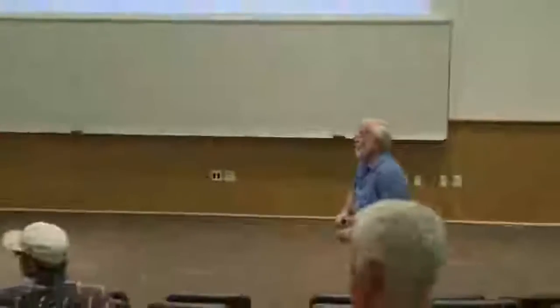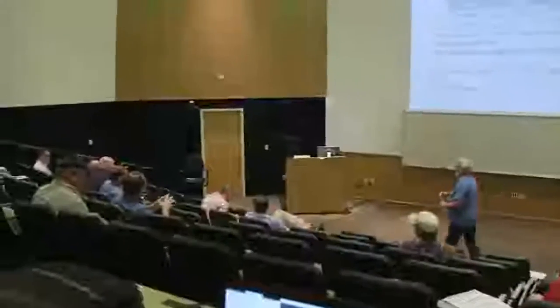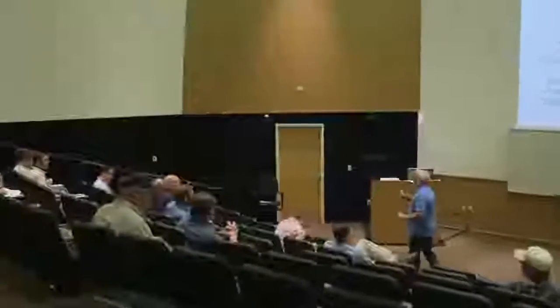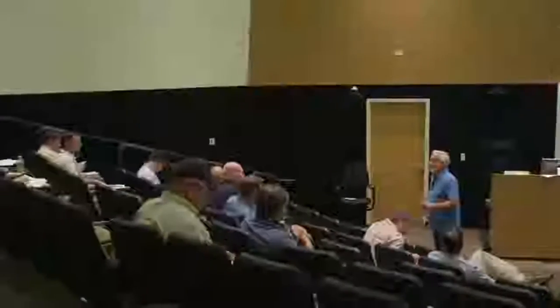Great question, Gordon. And it's something that confuses a lot of people. And there is a formula, and it kind of changes depending on how big the house is, doesn't it, a little bit? Yeah. Is there a formula that compares what this leak rate would be in comparison to this kind of thing? That you can get close to what your natural leakage would be based on that. And in fact, the combustion air section in the code actually wants you to, they have a formula. If you know the natural leakage rate, you can identify if you can use inside combustion air. So I've seen it, and it's kind of an approximation, but we can get fairly close.